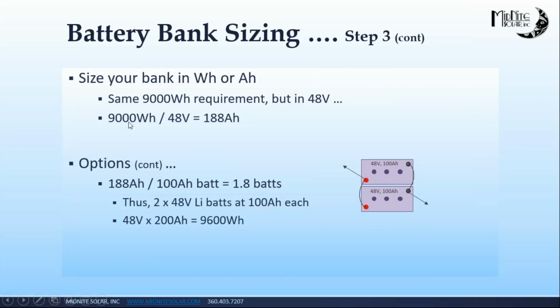Now, doing the same, I need the same battery bank, 9,000 watt hours, but this time we're going in 48 volts. Divided by 48, I get 188 amp hours. A lot of lithium batteries, very common today, are rated about 100 amp hours. A single battery is 48 volts, so in this example I need 188 amp hours. I find a 100 amp hour battery online, and it says I need 1.8 batteries.